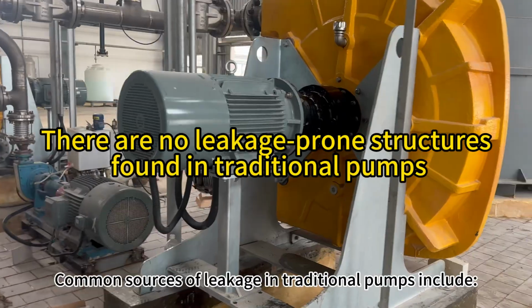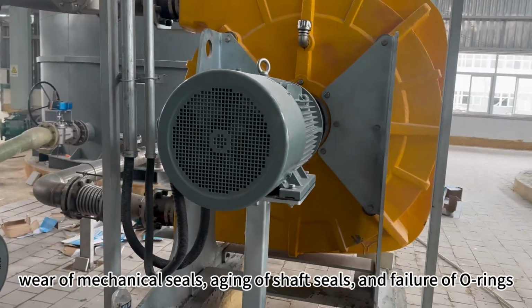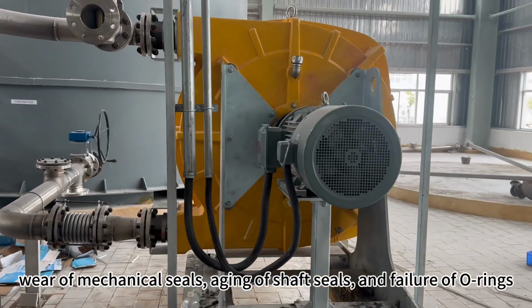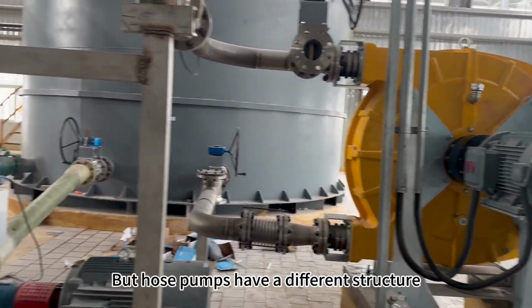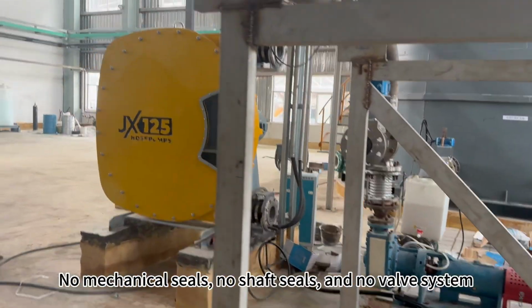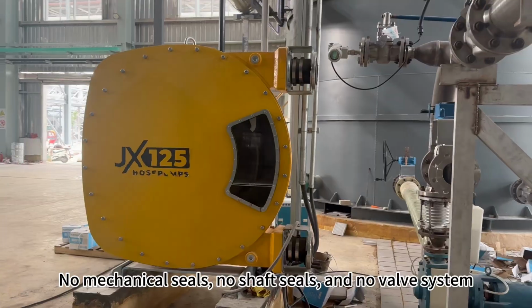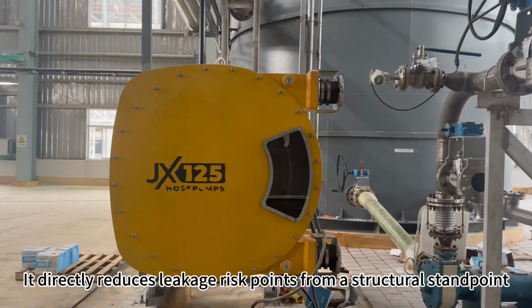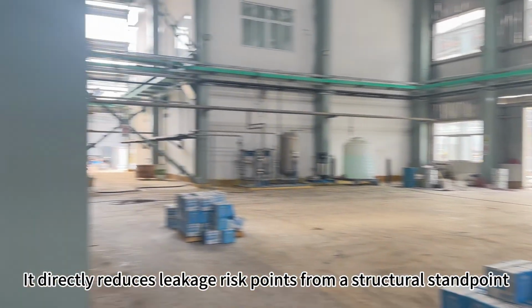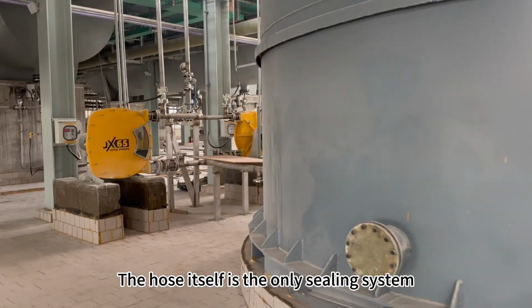Common sources of leakage in traditional pumps include wear of mechanical seals, aging of shaft seals, and failure of O-rings. But hose pumps have a different structure. No mechanical seals, no shaft seals, and no valve system. It directly reduces leakage risk points from a structural standpoint. The hose itself is the only sealing system.